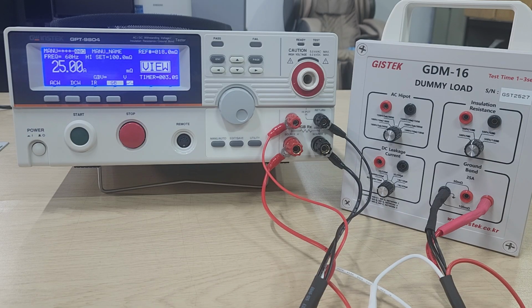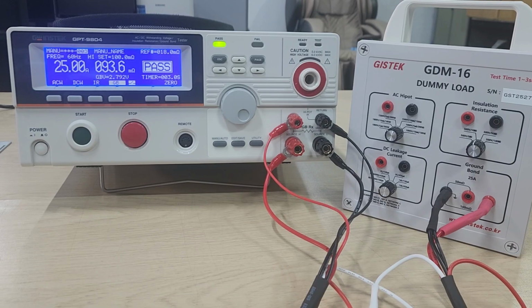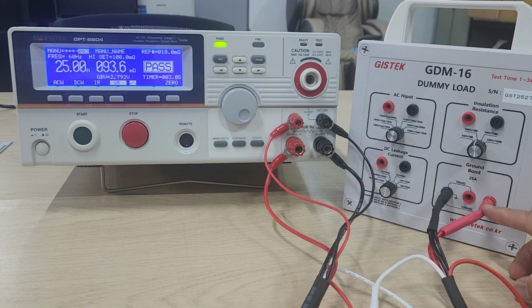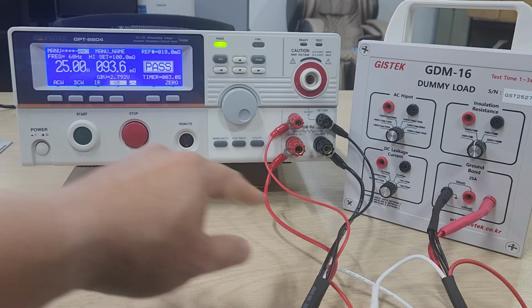Perform the inspection and check with the inspection result whether the AC ground resistance tester measures the value set at the dummy load closely. The test result may typically have an error of around 15 to 20 milliohm depending on the resistance value error of the dummy load, the output error of the AC ground resistance tester, the measurement error, the cable resistance value and contact resistance. So the error varies depending on the equipment and test environment.